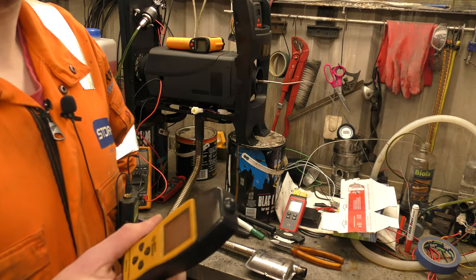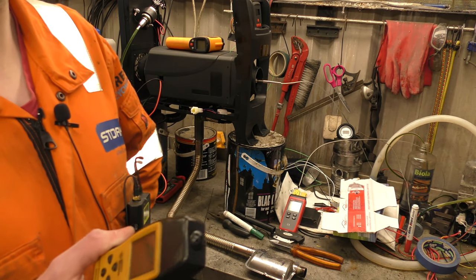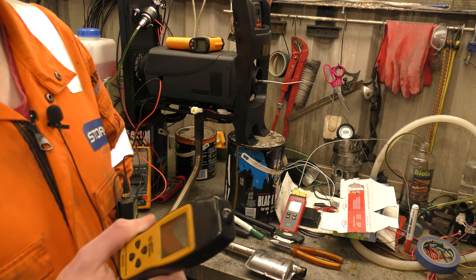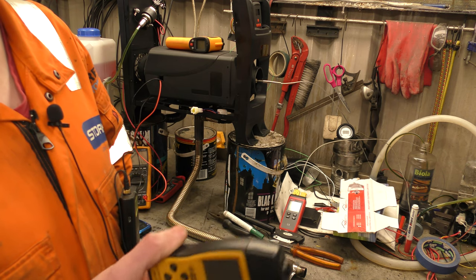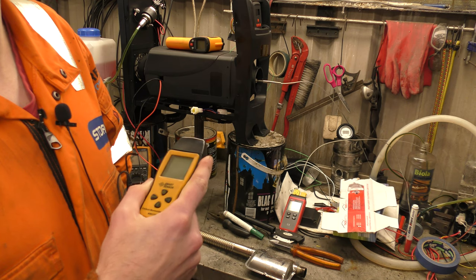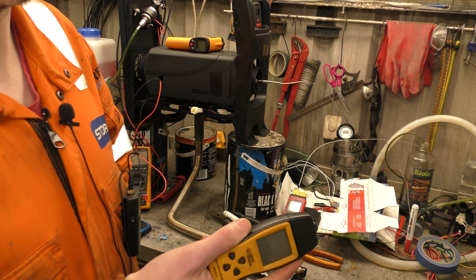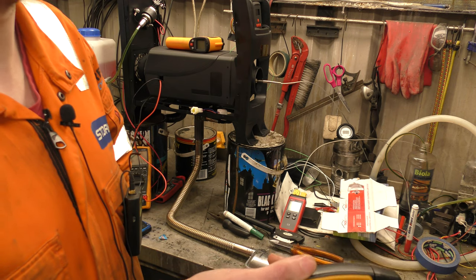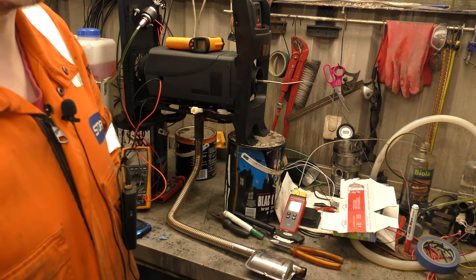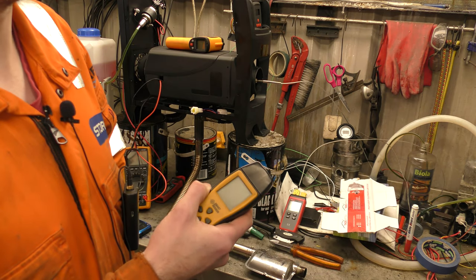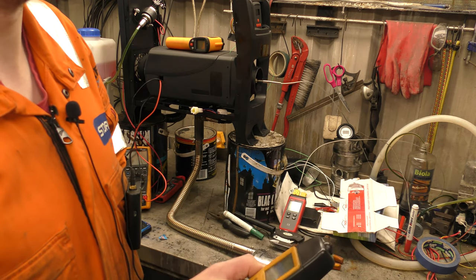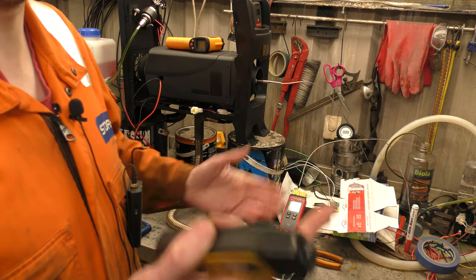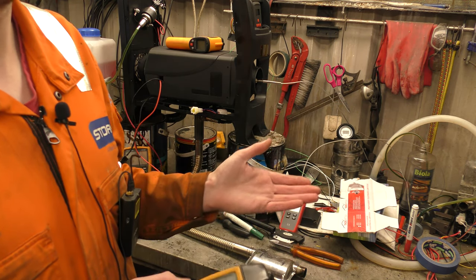Well, if you've made it this far and you're wondering, what does all this mean, David? Well, I don't know. Well, we know what it means. You need to get your air-fuel ratio right so that you have the correct burner temperature to make as least amount of carbon monoxide as you can for the amount of heat that you want to output. So, you can dial the fuel pump right back and have no carbon monoxide, but on the same hand, that also means you get less heat output from your heater.